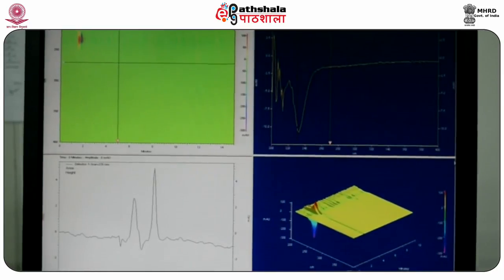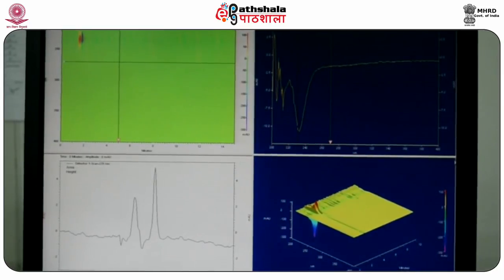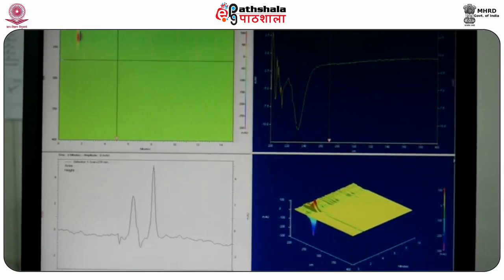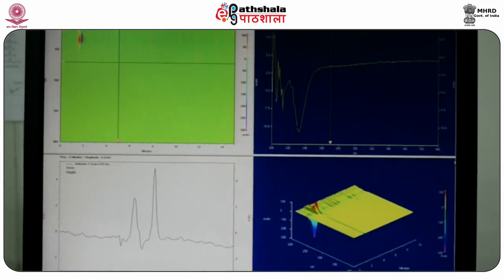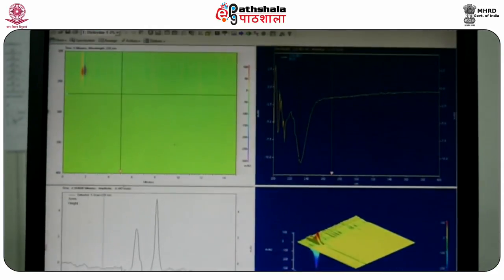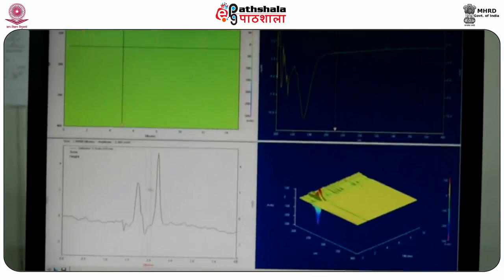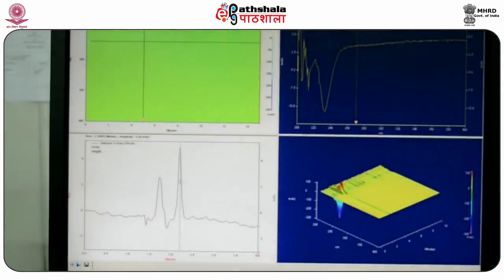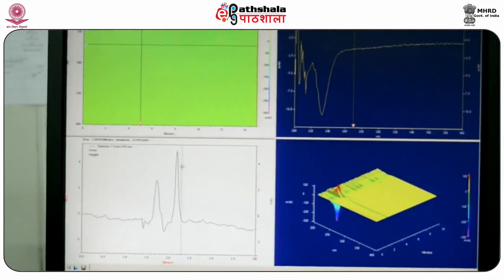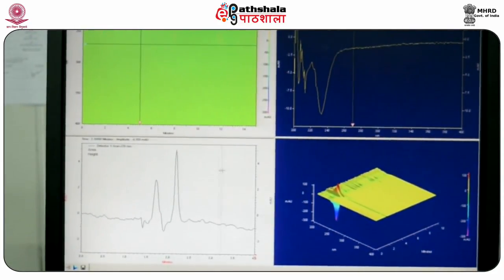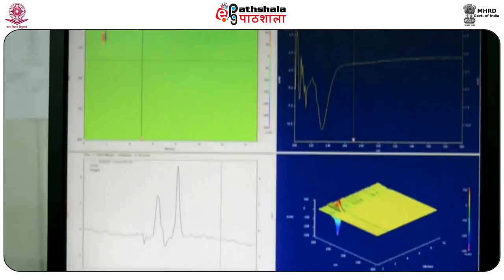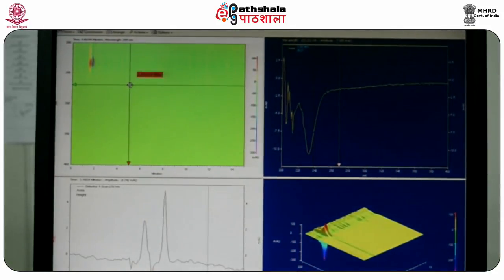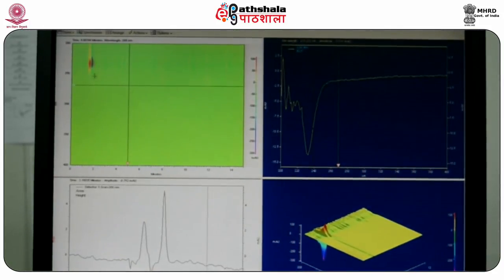The reagent bottles above feed a quaternary pump capable of handling four solvents together, enabling isocratic as well as gradient runs at flow rates from less than 0.1 ml per minute up to 2 ml per minute. The signal obtained from HPLC is processed by software, giving both UV data as well as mass data.